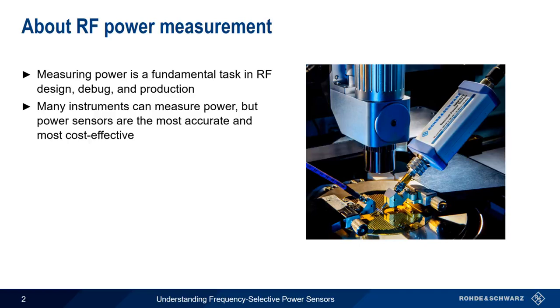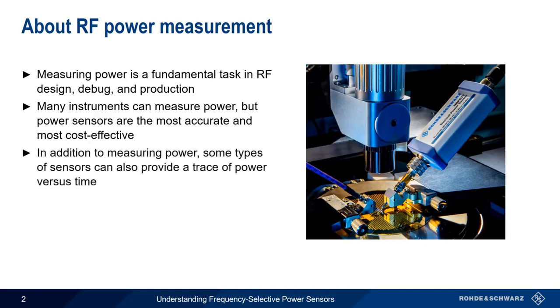In addition to simply measuring power, some types of power sensors have additional functions, such as the ability to generate a power versus time trace. This is useful when viewing the envelope of a pulsed or other time-varying signal.